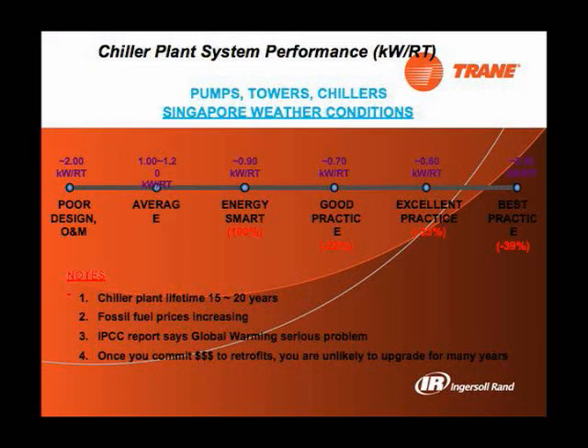Quick summary, if you see 2 kilowatt per ton, even under tropical conditions, that's bad for a chiller plant. Average in Singapore, 1 to 1.2. If you can go to 0.9, that was a year before, energy smart rating, now it's 0.75. If you can do 0.7, we would say that's good practice. And this is defined as an average each quarter. 0.6 would be excellent, and if anybody wants to shell out the money, we'll sign on the dotted line for 0.55.